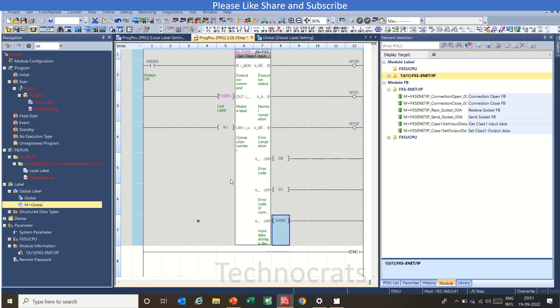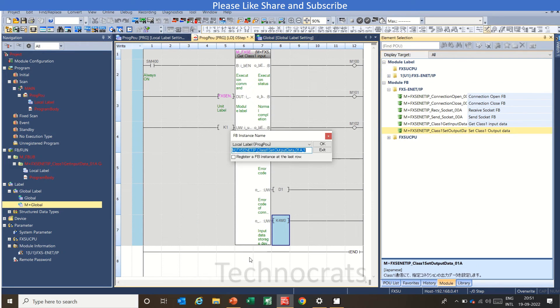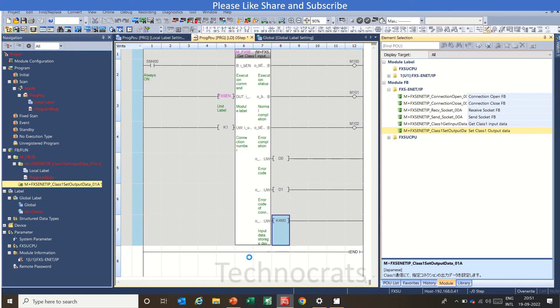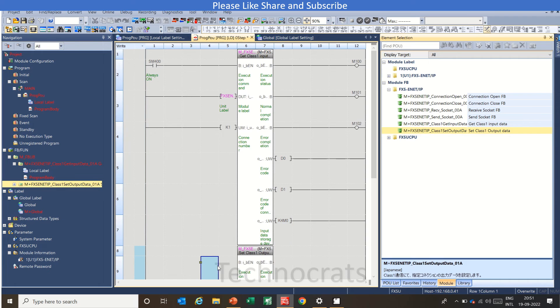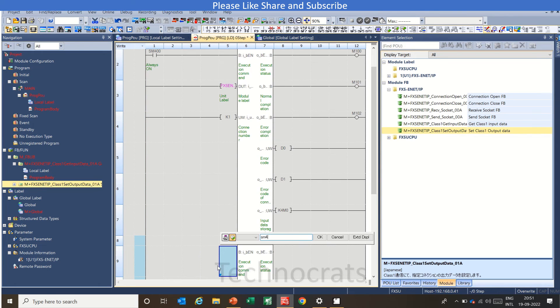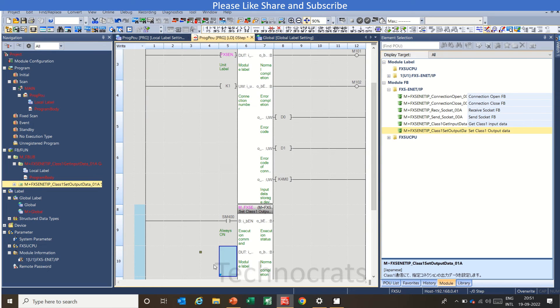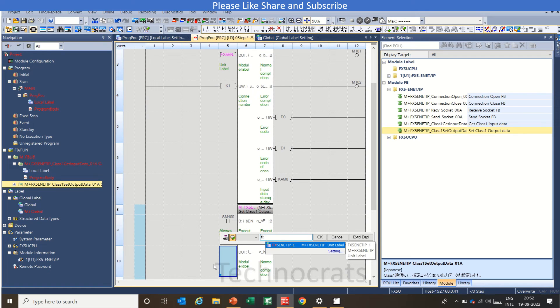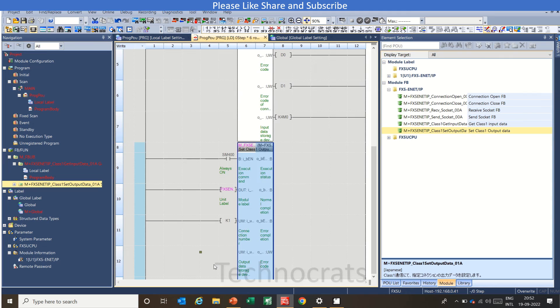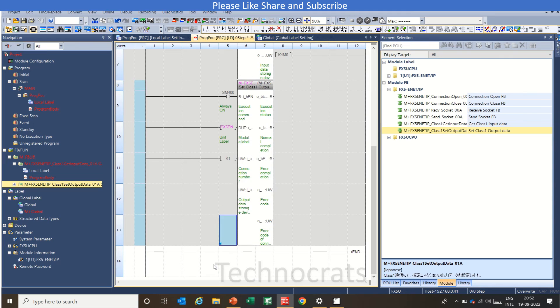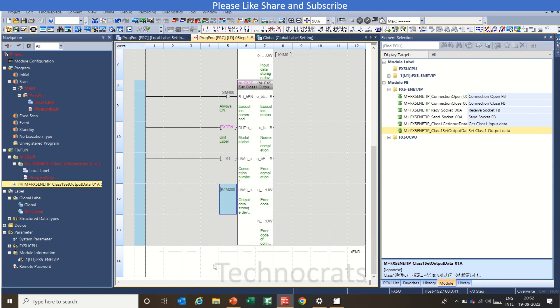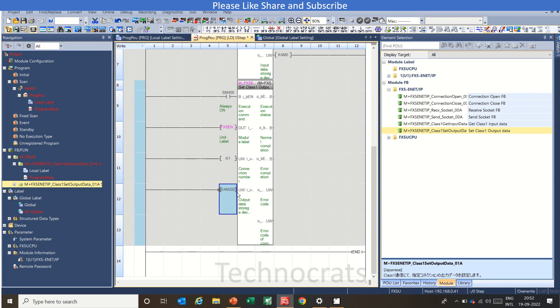Now going to the output section, just drop another function block that is for output. Write SM400 here that is always on flag, our module label that is FX5 Ethernet IP, and the connection number is again given. And this is our output. I will use K4M200. So basically this instruction will cover from M200 to M215 that is four nibbles and the output will be reflected to the module connected to the Ethernet card.